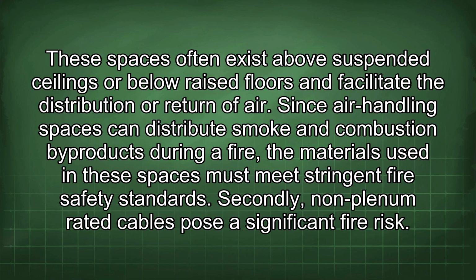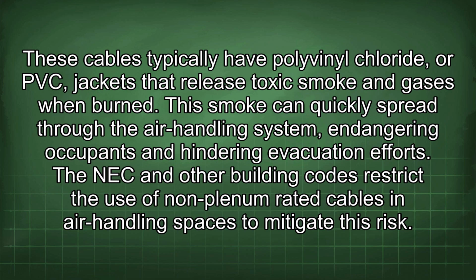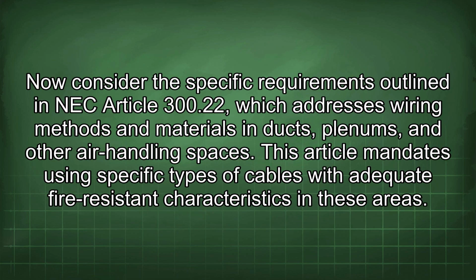Secondly, non-plenum rated cables pose a significant fire risk. These cables typically have polyvinyl chloride, or PVC, jackets that release toxic smoke and gases when burned. This smoke can quickly spread through the air handling system, endangering occupants and hindering evacuation efforts. The NEC and other building codes restrict the use of non-plenum rated cables in air handling spaces to mitigate this risk. Now consider the specific requirements outlined in NEC Article 300.22, which addresses wiring methods and materials in ducts, plenums, and other air handling spaces.